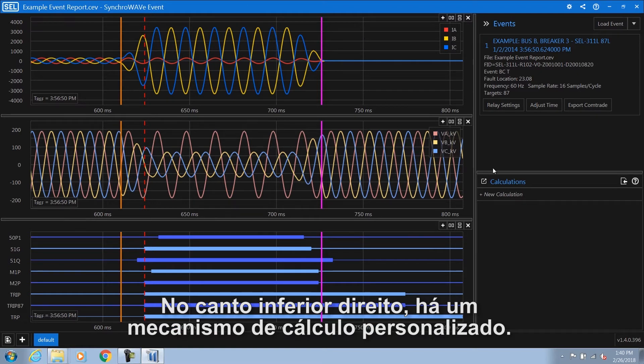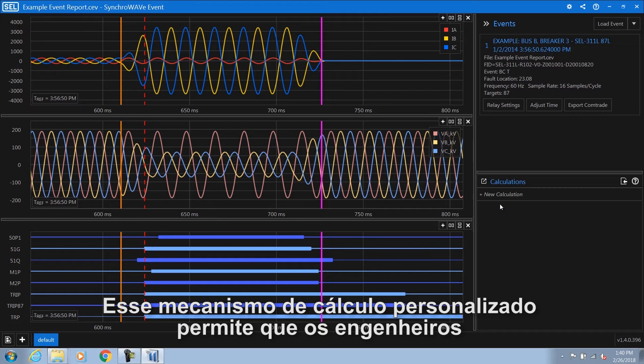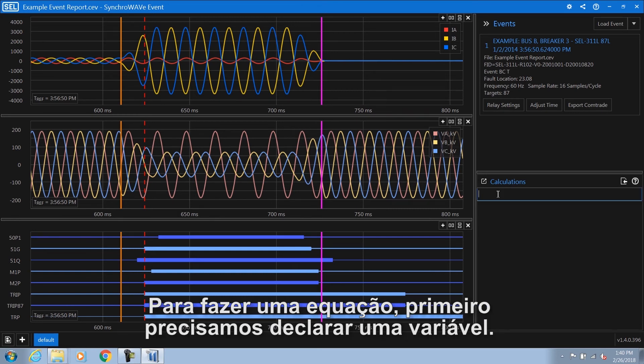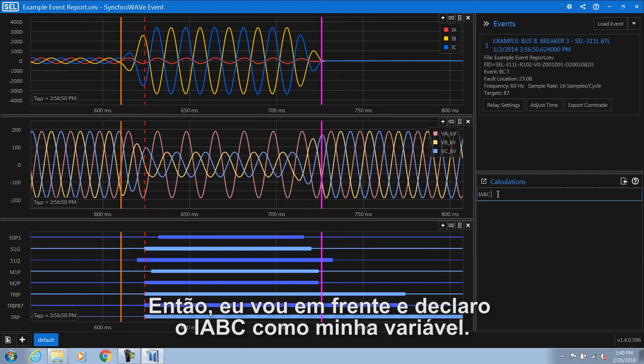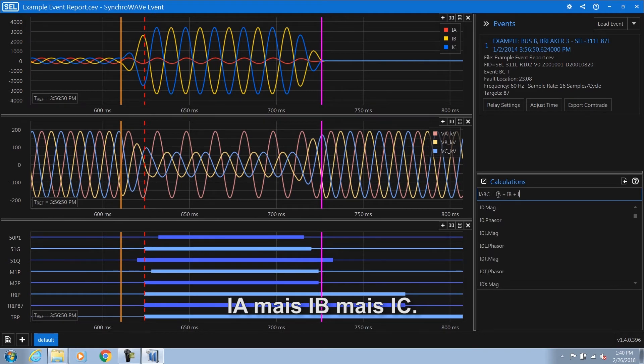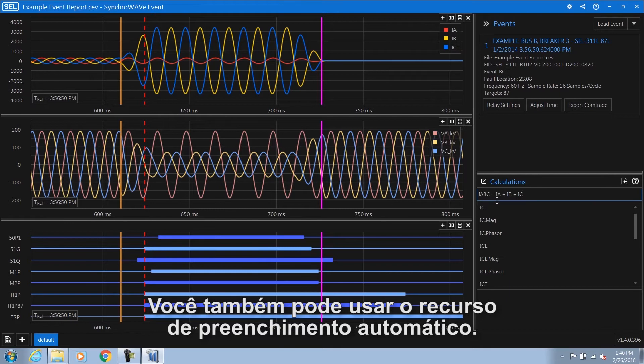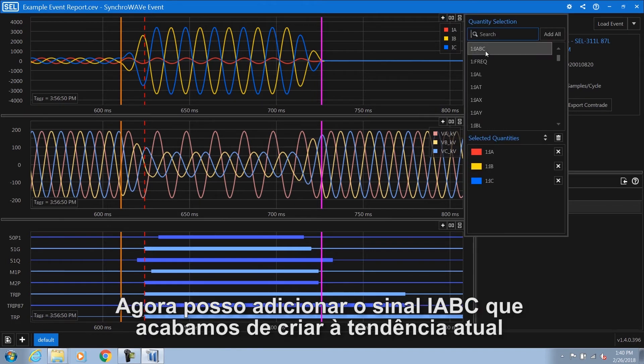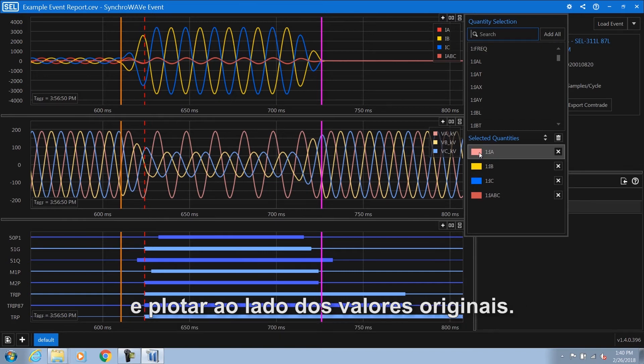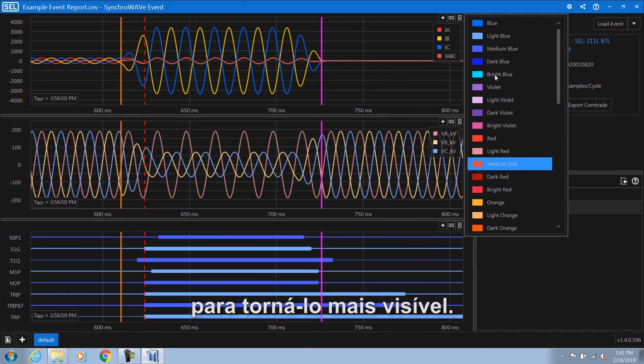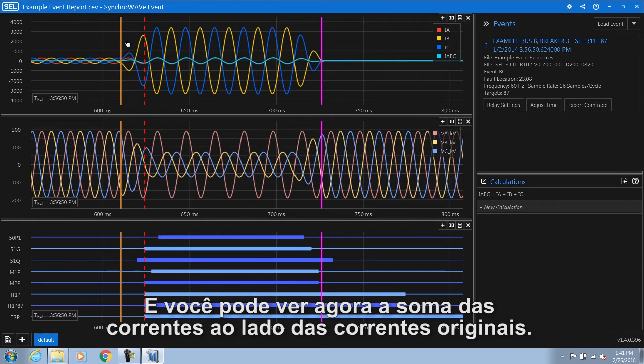In the lower right hand corner there's a custom calculation engine. This custom calculation engine enables engineers to take any analog or digital signal in the relay event report and use it in an equation. In order to do an equation, we first need to declare a variable. I'm going to declare IABC as my variable, and then sum up the phase currents: IA plus IB plus IC. You can also use the autocomplete feature. Pressing enter finalizes the equation and makes it available in your trend chart. Now I can add the IABC signal to the current trend and plot it alongside the original values, and change the color of the IABC to make it more visible. You can now see the summation of the currents alongside the original currents.